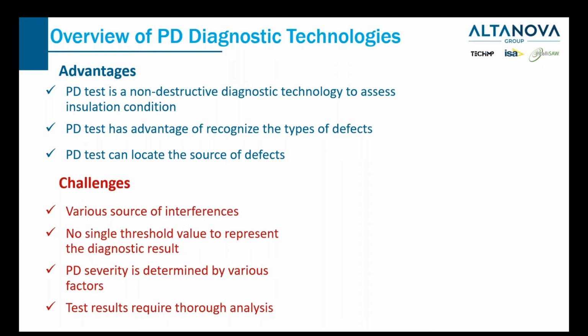A principle of diagnostic testing is we do not damage the equipment on the test. So PD is a non-destructive testing. It will not reduce the effective service life of the equipment on the test.